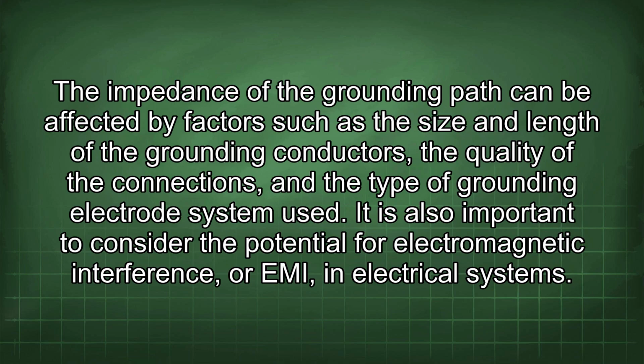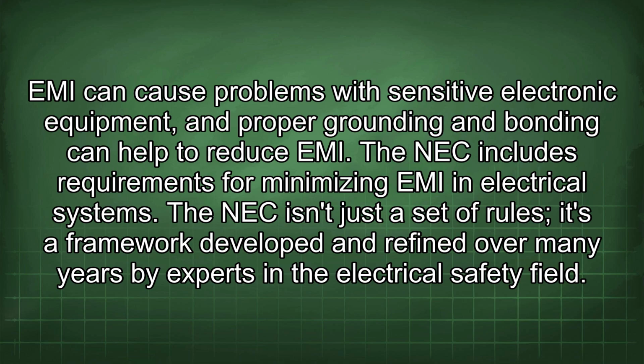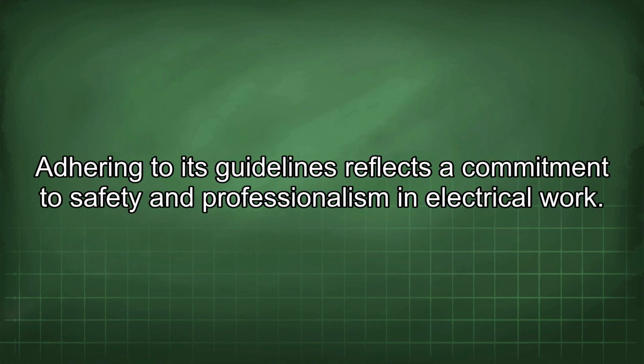to the source. The impedance of the grounding path can be affected by factors such as the size and length of the grounding conductors, the quality of the connections, and the type of grounding electrode system used. It is also important to consider the potential for electromagnetic interference, or EMI, in electrical systems. EMI can cause problems with sensitive electronic equipment, and proper grounding and bonding can help to reduce EMI. The NEC includes requirements for minimizing EMI in electrical systems. The NEC isn't just a set of rules, it's a framework developed and refined over many years by experts in the electrical safety field. Adhering to its guidelines reflects a commitment to safety and professionalism in electrical work.